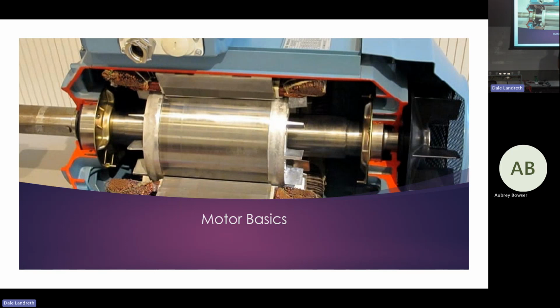Somebody says, what's it do? Test insulation. How does it test the insulation? See if there's a short, sends voltage. It puts a voltage in the windings at a very minimal current, and you're testing for the leakage of that voltage, either to ground or between the windings. Does everybody understand that? That's 100% right.